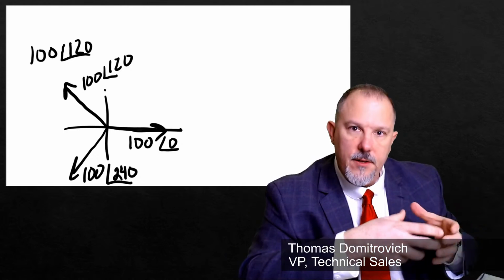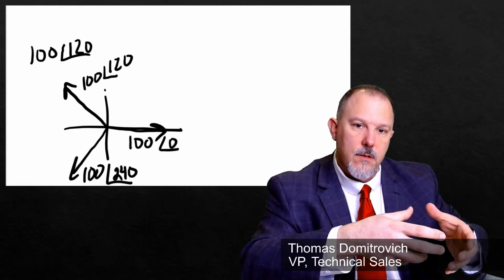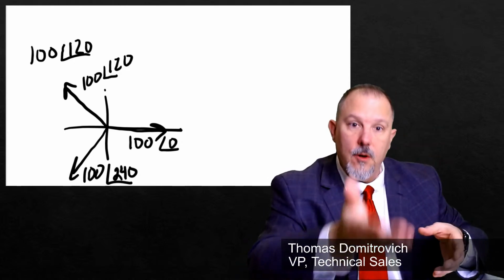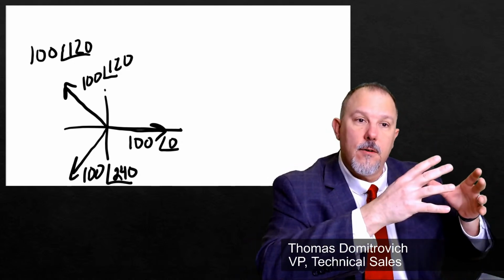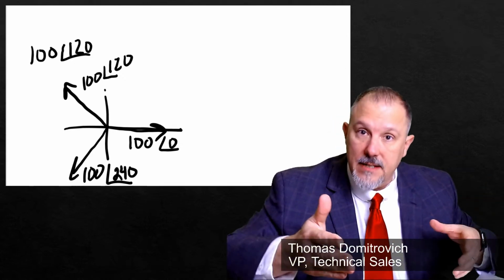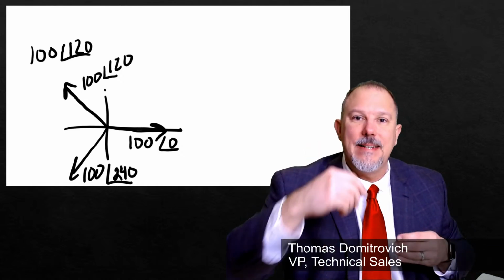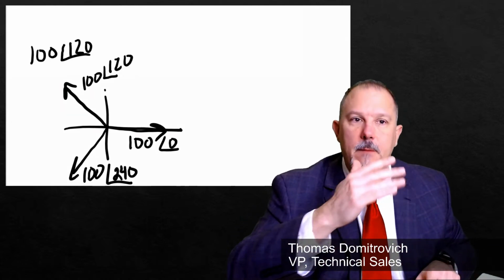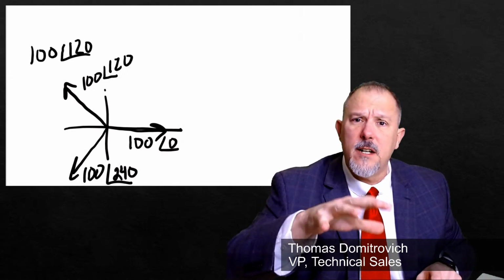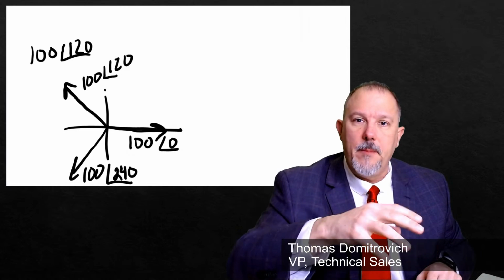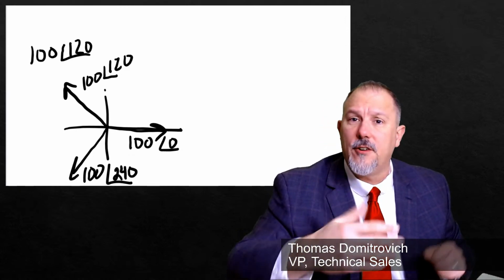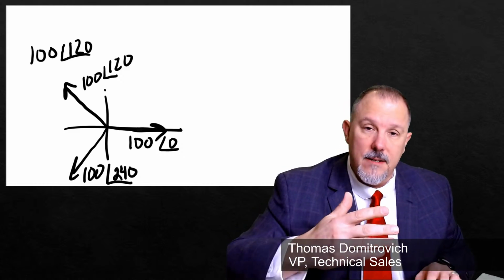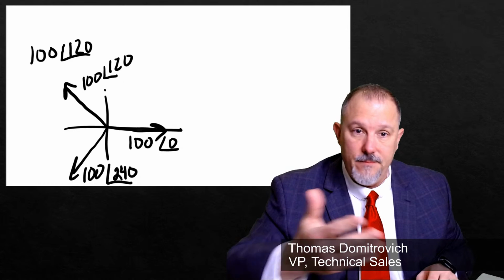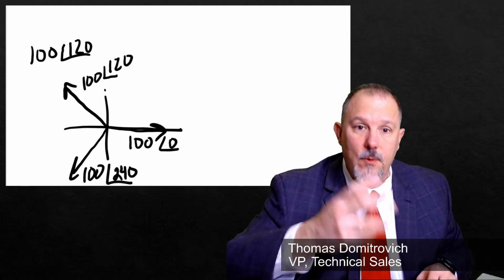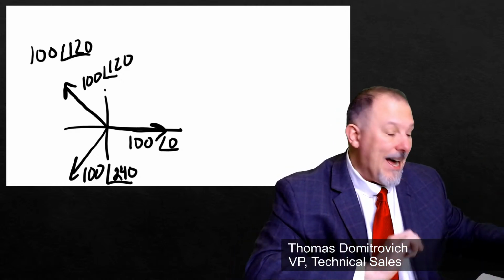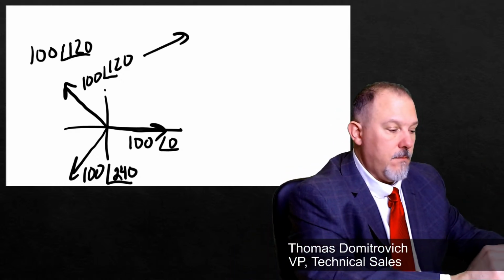So if I put a donut around three-phase conductors, and they are at 0, 120, and 240, they have this angle displacement between phases. When you add them up, you get 0. Now, if there is a slight difference, your calculation may be a little bit off with regard to how much current you calculate in the differential. But for the most part, in three-phase systems, when you add these three up vectorially, they will be 0.